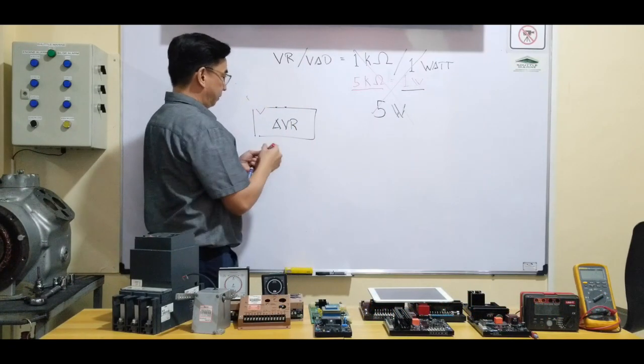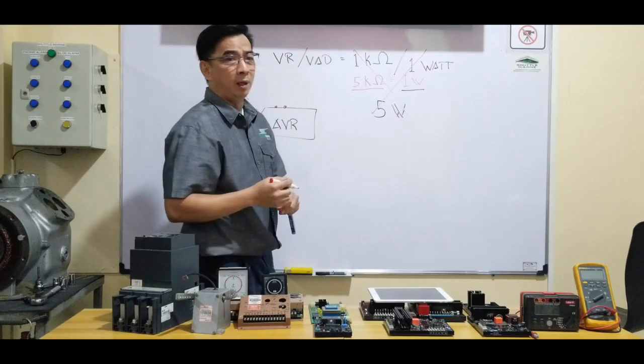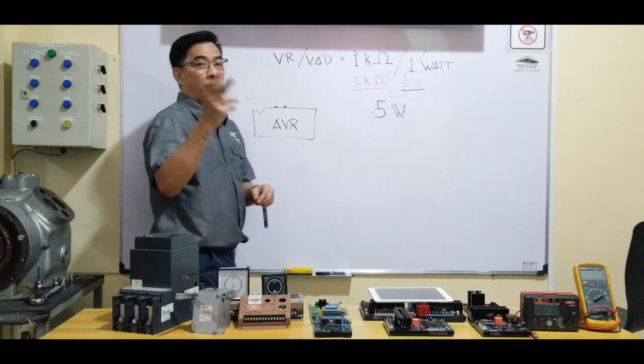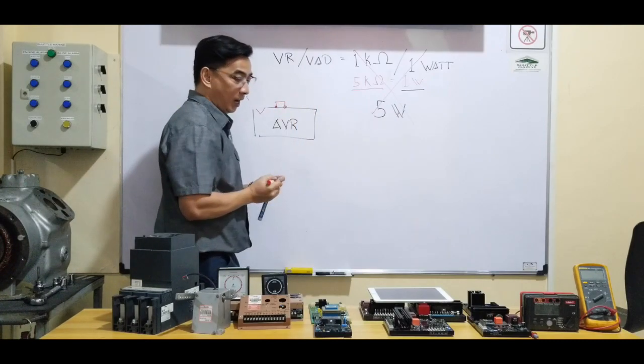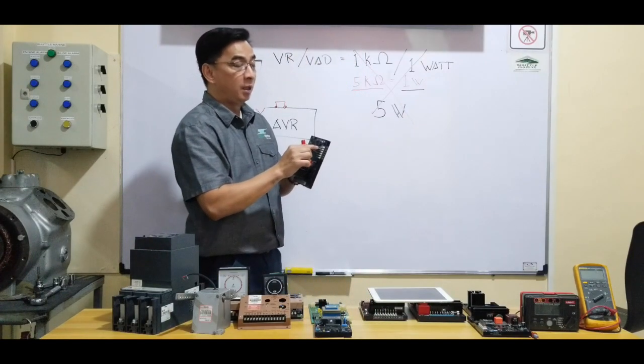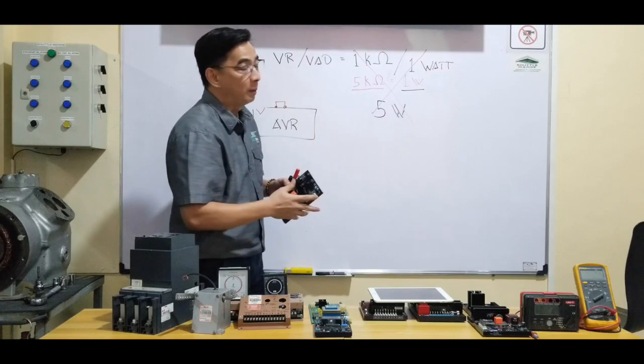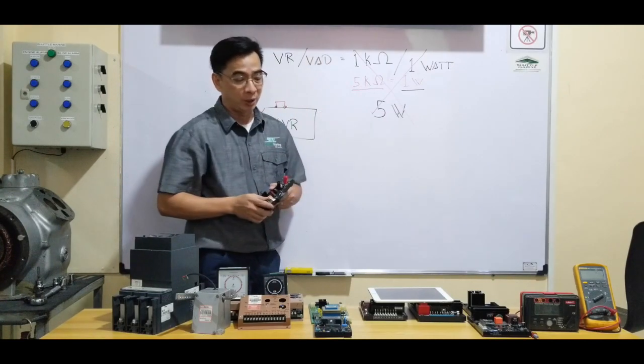Okay? Just remove those two wires that directly work to your potentiometer, remote potentiometer, and install a jumper. Actually, the AVR out of the box, it has a jumper. The remote potentiometer is just an optional if we want a remote voltage adjustment.